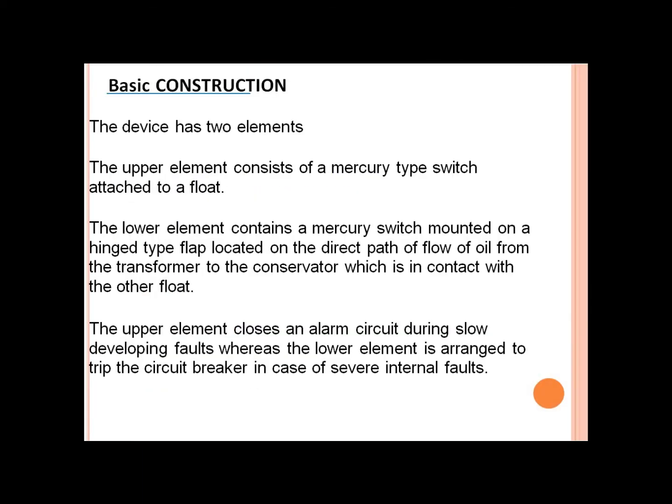The basic construction is as discussed. The upper element consists of a mercury-type switch attached to a float. The lower element contains a mercury switch mounted on a hinge-type flap, located on the direct path of flow of oil from the transformer to the conservator. The upper element closes an alarm circuit during slow developing faults, whereas the lower element is arranged to trip the circuit breaker in case of severe internal faults.